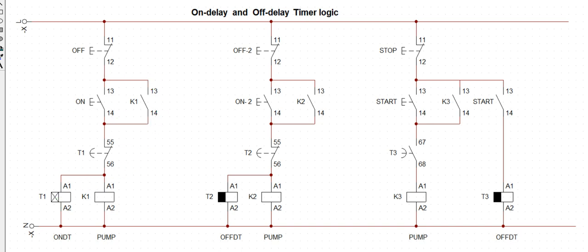You can see that, watch again, when I energize, the relay gets energized and this one is counting. Okay, it now shut down. Once this one shuts down, the logic shuts down. And that is exactly what off delay does, but in another logic representation. All right, in summary, whenever I want to use a function of cooling down duration, you want a particular plant or a particular equipment to shut down after a preset time. This is the logic you will put up.